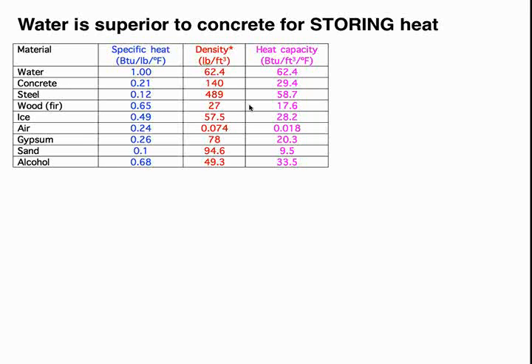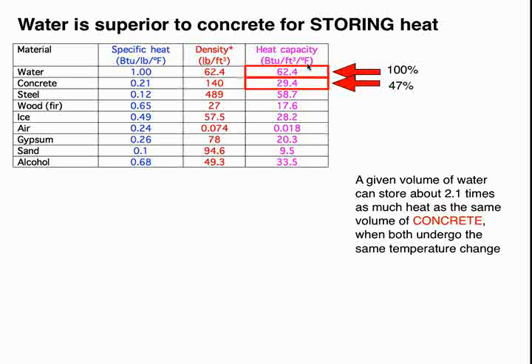Water is really one of the best things on Earth for storing heat. And just to show that, I'm going to do a comparison between water and concrete. And the two red rectangles that you see over here, these are comparing what we call heat capacity. That is the amount of heat that it takes to raise a given volume of a substance 1 degree Fahrenheit. And in English units, how many BTUs would be required to raise a cubic foot of a material 1 degree Fahrenheit? For water, it's about 62 BTUs per cubic foot per degree Fahrenheit, and roughly half that for concrete.